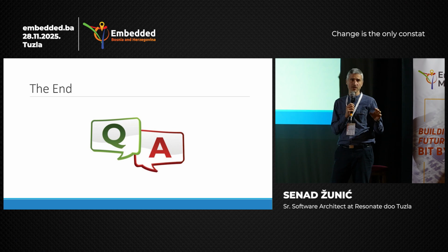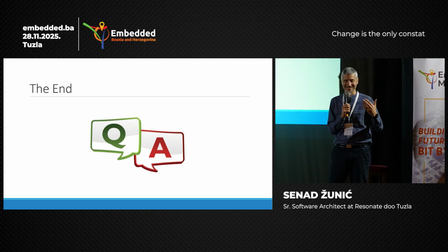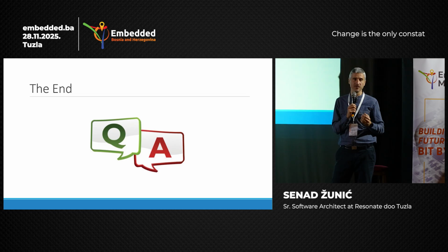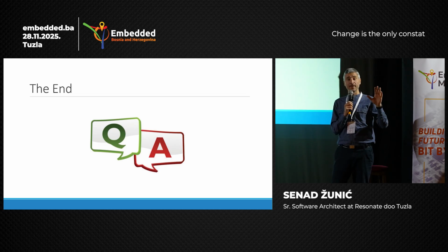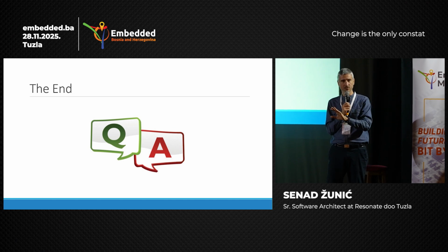FreeRTOS is well documented, so during your analysis of the SOUP that you used, you say which version you use, you say what the limitations of that are, so you're kind of accepting the limitations of the library you used. And then you check, does that library have a certificate or not? You already said that it doesn't. So you need to check residual risks with that. Do any of those limitations affect what your intended use is?